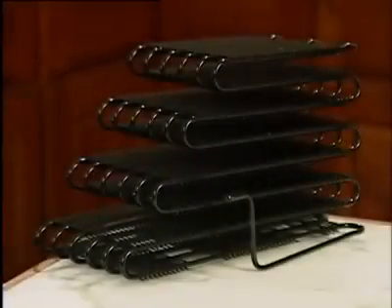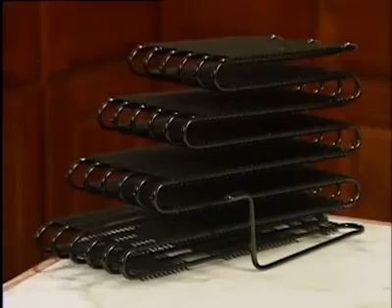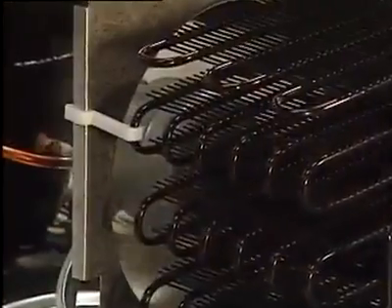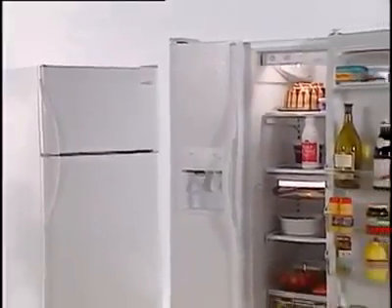The condenser is a critical component of a sealed system. It must be capable of removing heat from the hot refrigerant. To do that, it must stay free of dust and dirt. If a blanket of dust collects on the condenser, it will prevent it from giving up its heat to the surrounding air. How often the condenser must be cleaned depends on its design and construction.